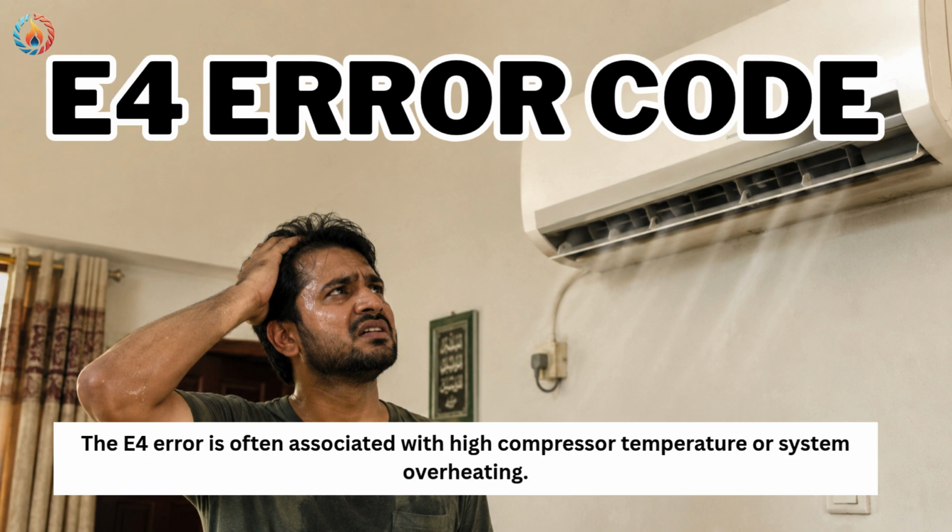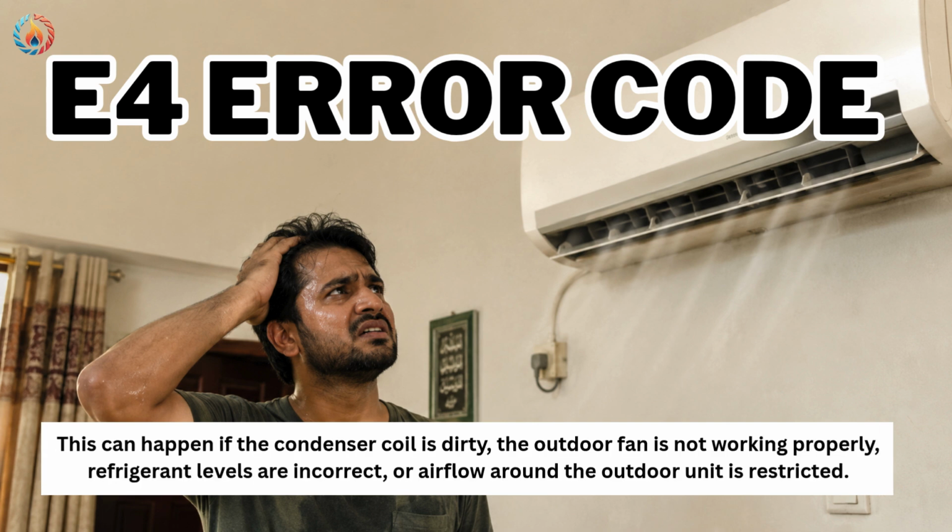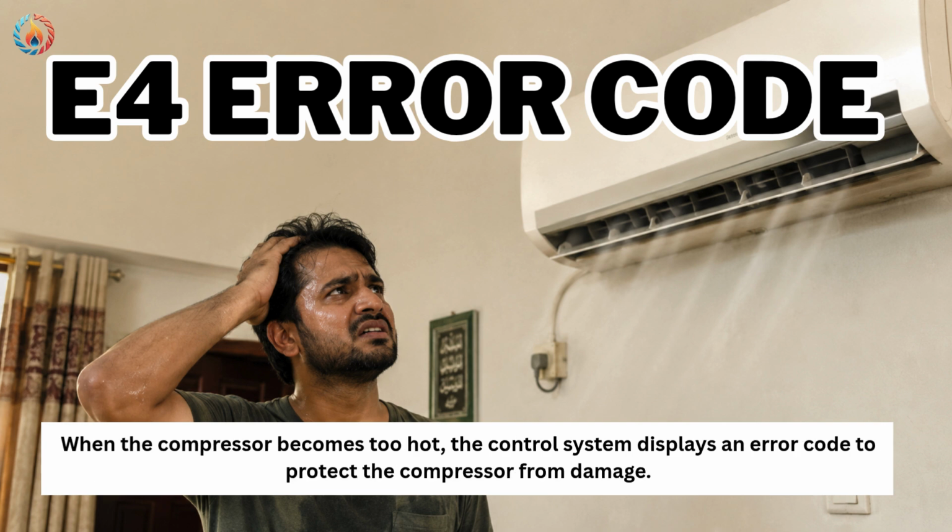E4 error code. The E4 error is often associated with high compressor temperature or system overheating. This can happen if the condenser coil is dirty, the outdoor fan is not working properly, refrigerant levels are incorrect, or airflow around the outdoor unit is restricted. When the compressor becomes too hot, the control system displays an error code to protect the compressor from damage.